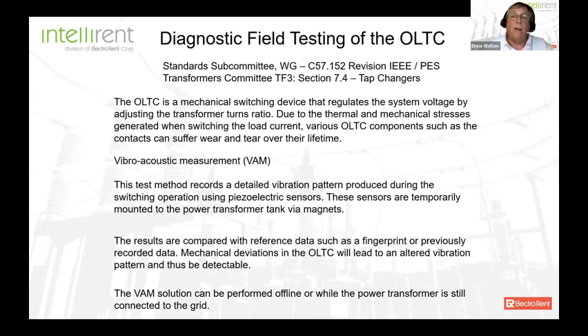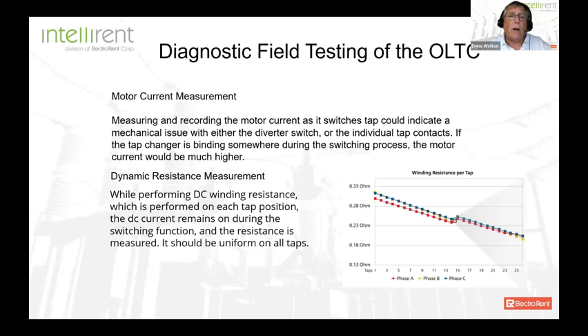One is a vibroacoustic measurement. As you move the transformer from one tap position to the next, you have these little vibroacoustic sensors on the tank that measure and record the vibration and the amount of acoustics. If some are higher than others, it's going to tell you to investigate further. The vibroacoustic measurement is actually very easy to run, depending on the equipment you have and how easy the access to the cabinet is.